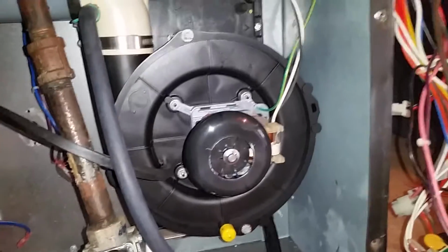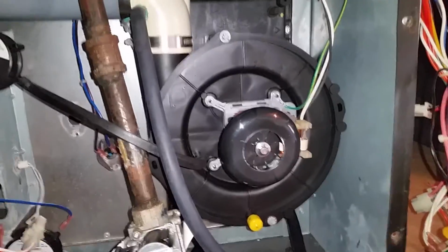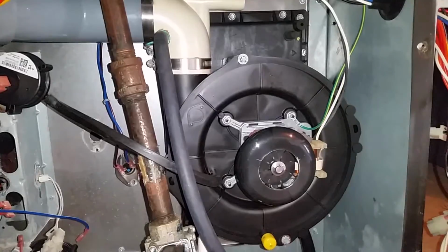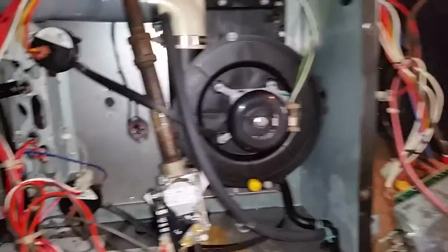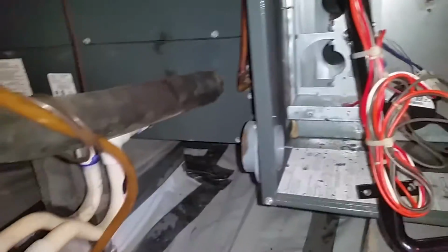But primarily what we've got is the water as it's condensed. Since this is a condensing furnace, it mixed with the flue gases, which, because of the improper combustion, turned the water into acid, and they began to eat away at the heat exchanger. And all of this was caused simply because nobody had installed fresh air on an encapsulated crawl space.